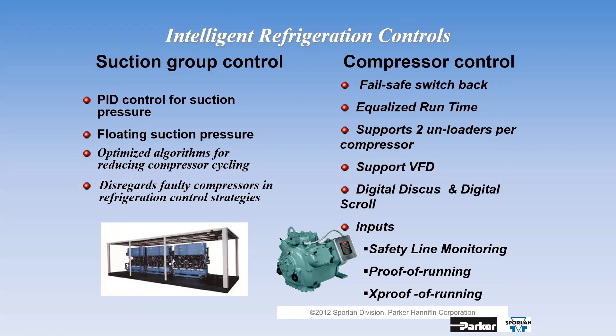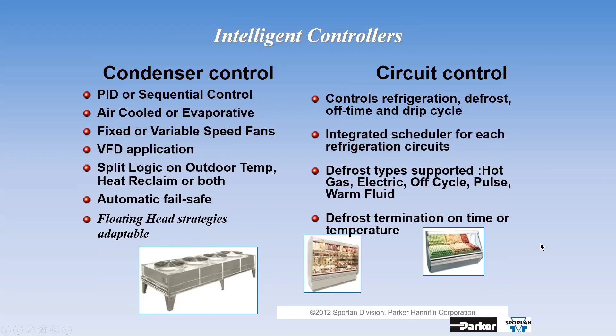Condenser or gas cooler control, PID or sequential. We can do air cool, evaporative, fixed or variable speed, VFD. We can split on either outdoor temp or heat reclaim, and we have all kinds of floating head strategies. Circuit control, we control refrigeration, defrost, all types of defrost: hot gas, warm gas, cool gas, electric, off cycle, pulsing warm fluid, etc. And we can defrost terminate on either time or temperature.